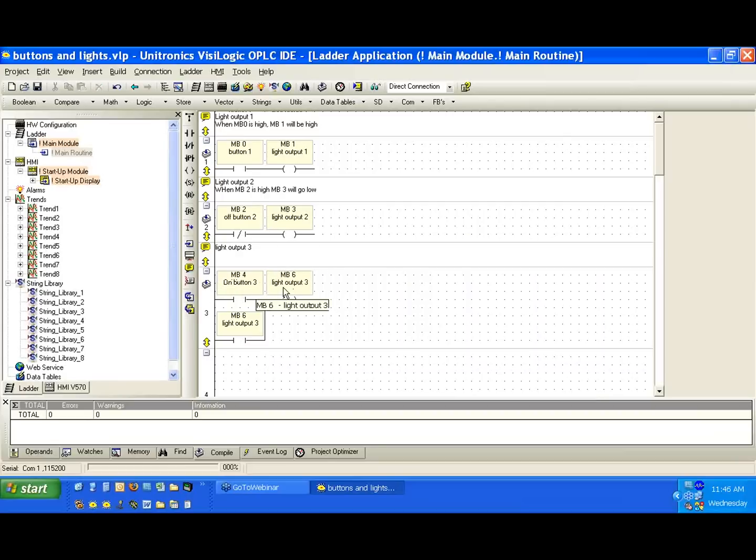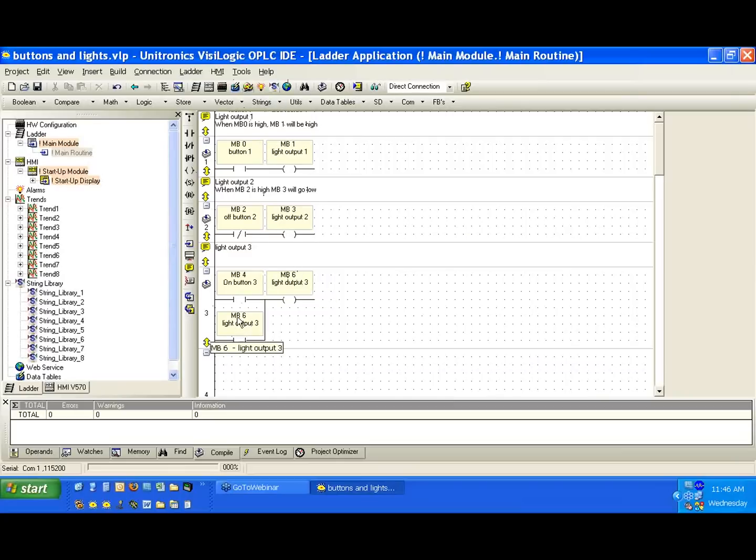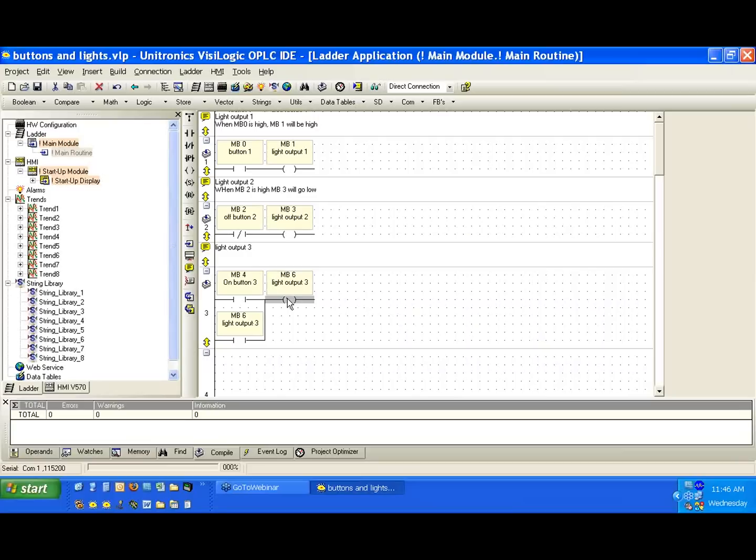So now with this statement, when we press MB4, MB6 will go high. And when MB6 is high, we're going to continue through the scan. The light output will be high. We'll come back around in the scan. It's a big cyclical scan. And since MB6 was high when we left, the contact of MB6, MB6 will be high. So the contact will keep the output high. We'll take a look at this when we download it. But let's just assume it's okay for now. What we need to do is add some way to stop this or to break it. What we're going to do is add the off button as the break.